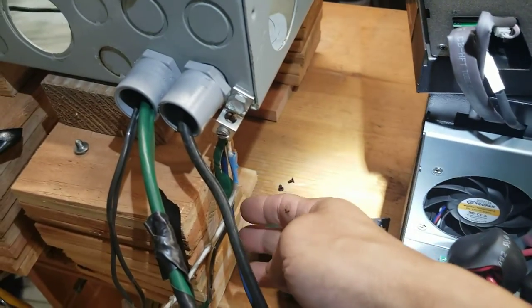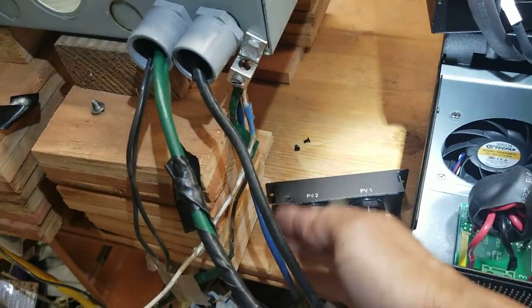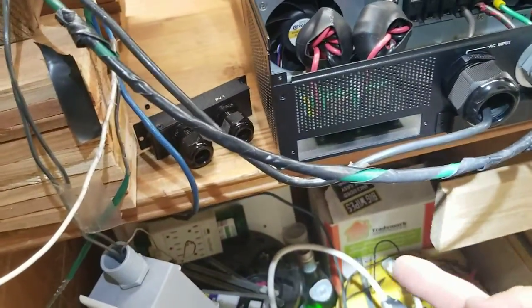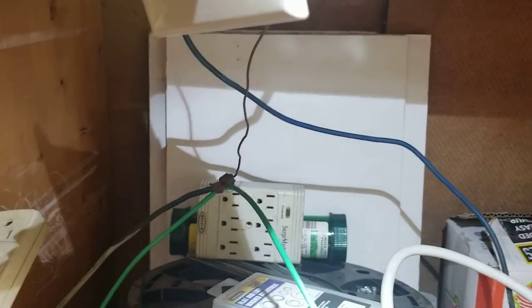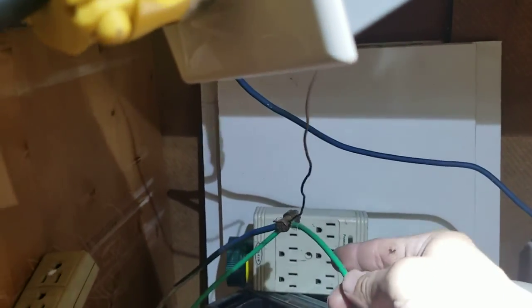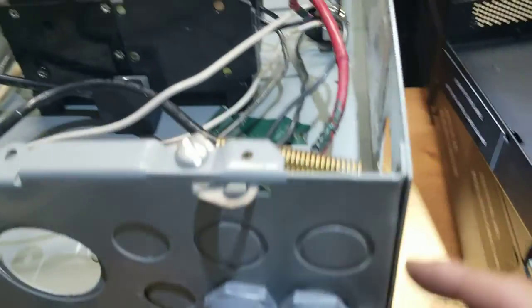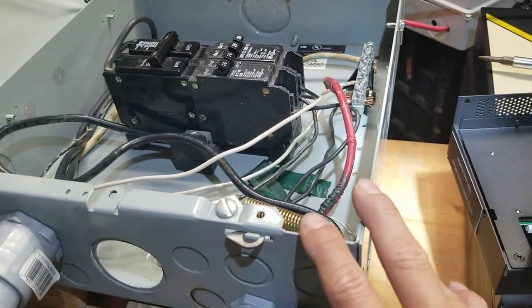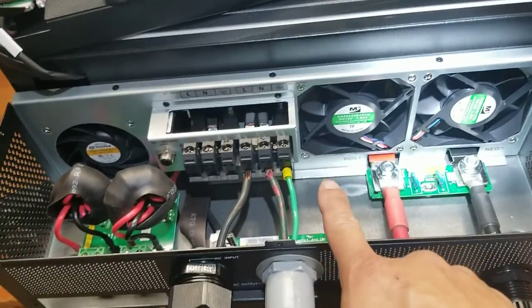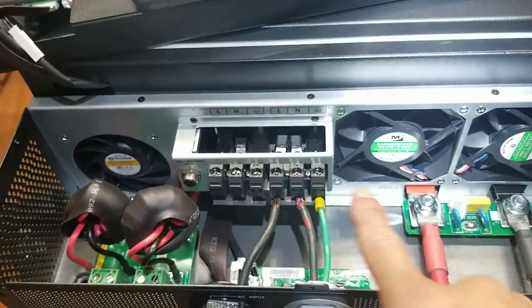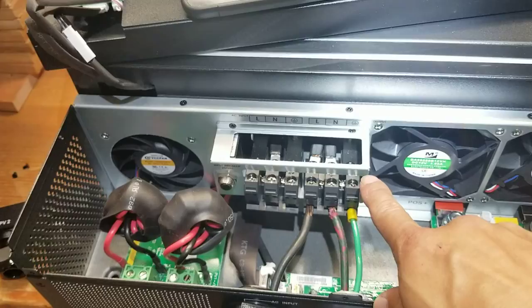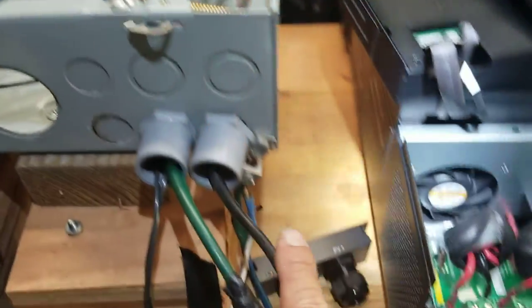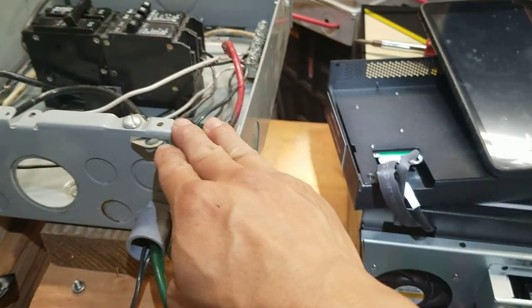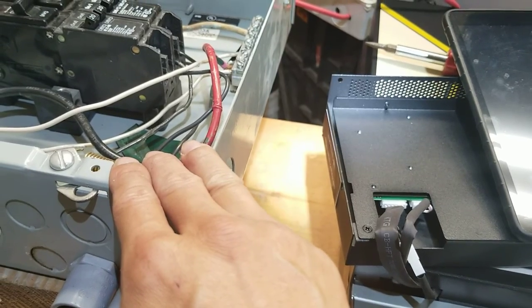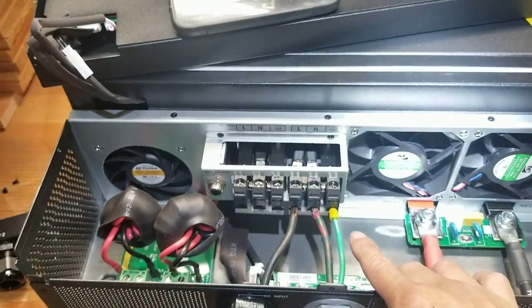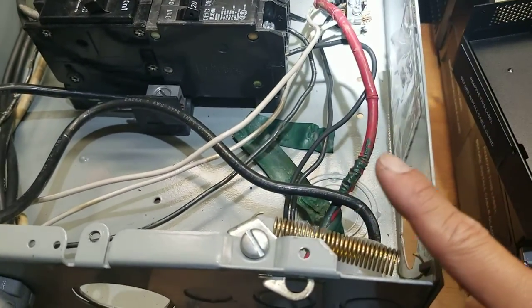On this one, I did connect them to ground. The blue wire is connected together with the ground right there—see, blue and green—and I connect it to the box. The first contact of the box circuit breaker needs to be grounded according to the California code, and after that you don't have to. This one is the first contact already, so you can connect to the box if it's close, but if it's far away you don't have to, according to the code—other YouTubers say that too. You guys need to find out about the code in your own state.